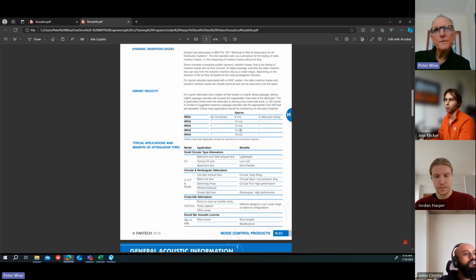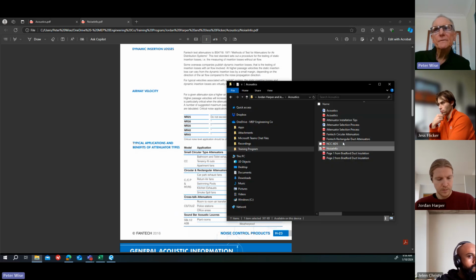So NR40, 15 metres per second. As you go down in NR rating, the velocity is going down as well. So that's the passage velocity between the splitters in the attenuator. NR45, they're saying 18 metres a second. Well, so you can go a bit higher. When we talk more about attenuator selections, this will become a bit clearer. Maybe I'll just talk briefly about it now.